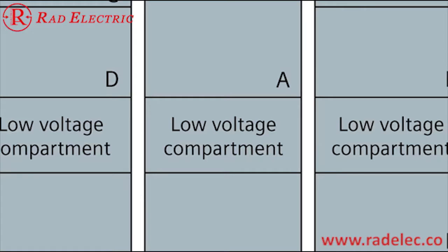Let's begin by looking at the skeleton, which is offered in 3 basic configurations and in a variety of stacking options for your switchgear project. No matter which structure you implement, OEM partners need to design and add approximately 28 inches of structure for the terminal compartment, plus bus bars and front and rear doors. This vertical section can then be bolted to additional vertical sections side by side. End sections require side sheets.